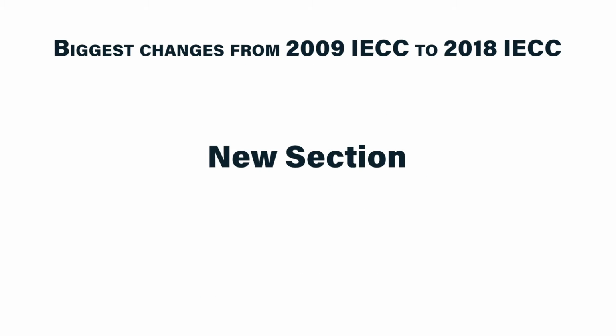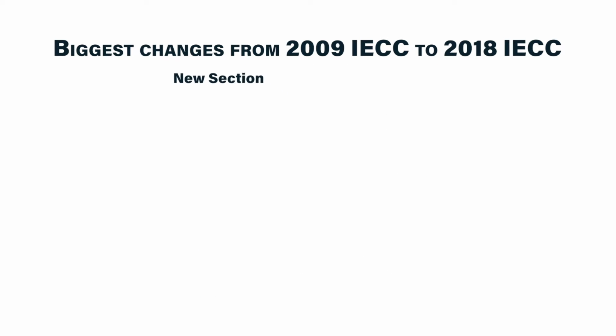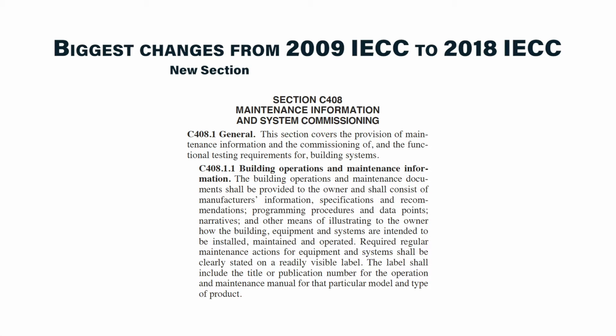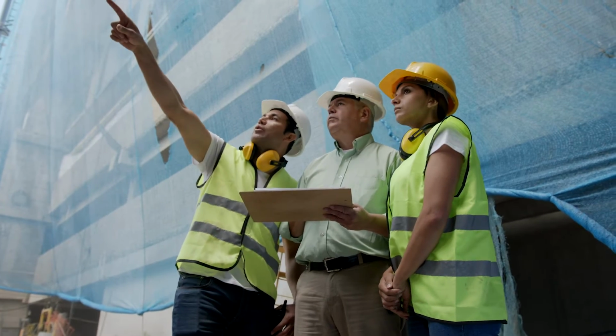The other new section in IECC 2018 is Maintenance Information and System Commissioning. This is a new mandatory section that applies to both prescriptive and performance paths and requires buildings to have a detailed mechanical, service water heating, and lighting systems commissioning plan. Having a good design is just the first step to achieving an energy-efficient building, but buildings don't always operate as designed. This is where third-party commissioning comes in.